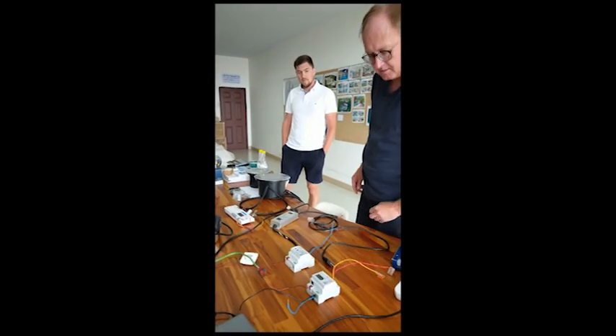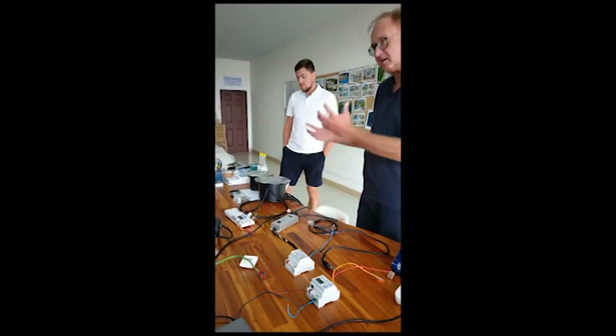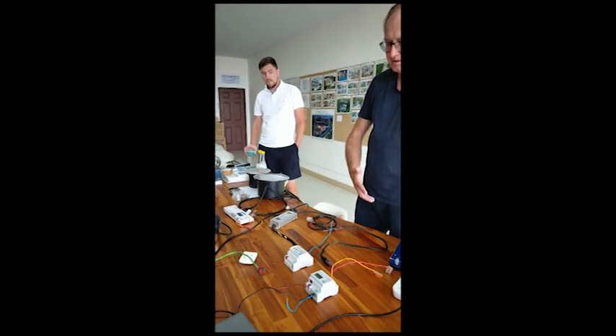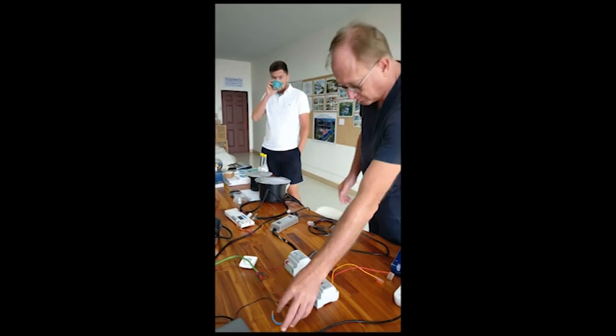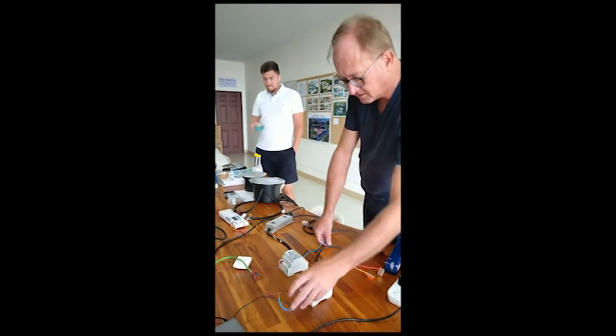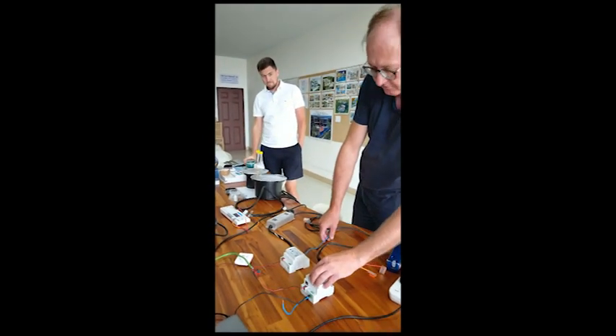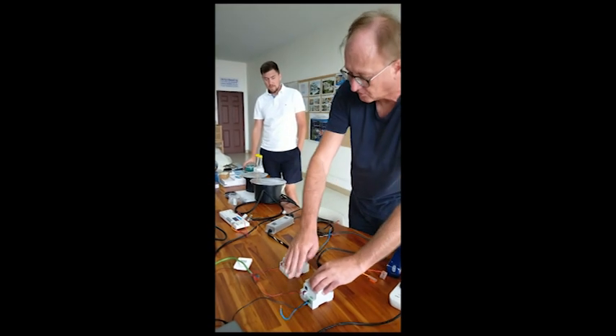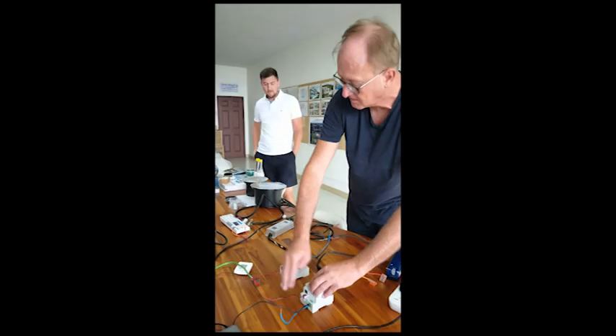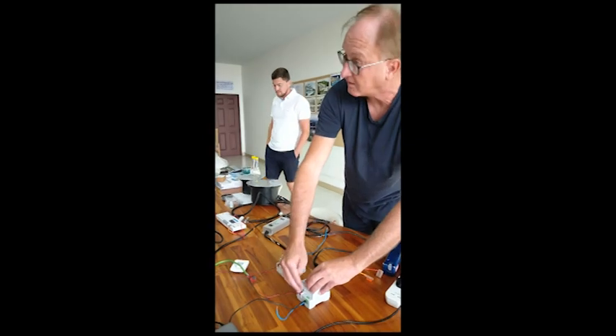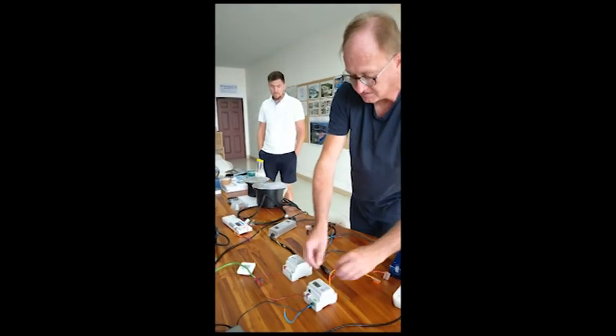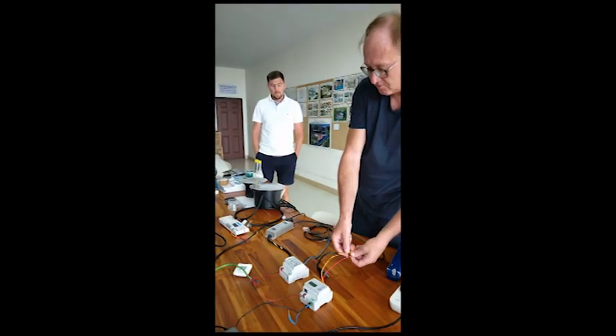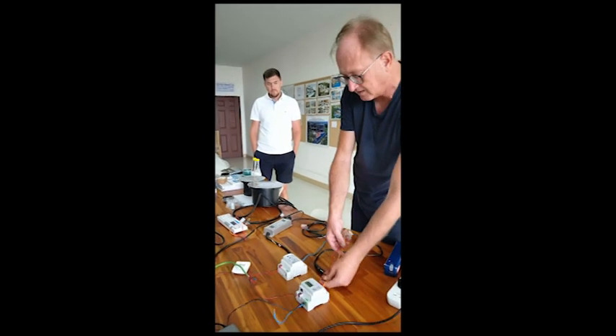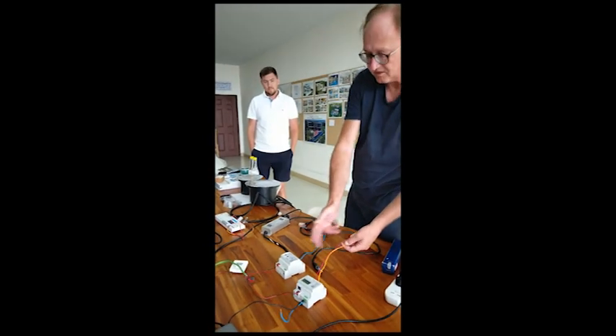The DALI gateway is the interface between the KNX world and the DALI world. It has a power supply like this, 230 volt, which powers the DALI gateway itself. It's connected on one side to the KNX bus, so it receives commands via KNX, and issues commands in DALI. All the DALI cables should have the same color.